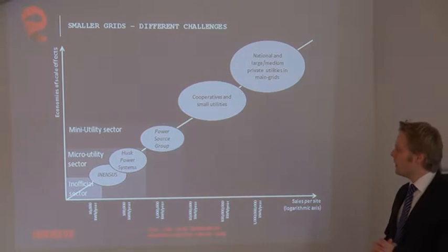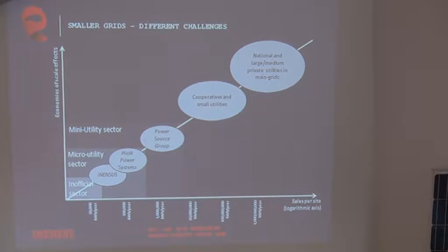So, for example, in our systems in Senegal, where we have approximately 1,000 people in one grid, we install some equivalent to 10 kilowatt peaks of photovoltaics. Sometimes we have small wind turbines in there, plus an 11 kVA diesel genset. And we have an 80% renewable fraction in that grid and a 20%...